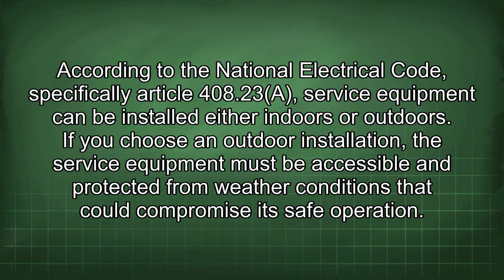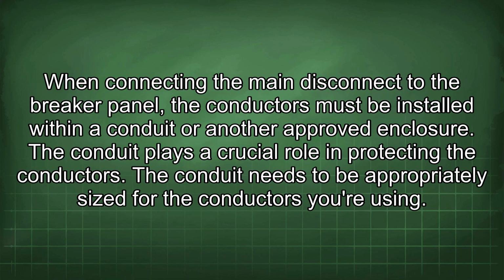According to the National Electrical Code, specifically Article 408.23a, service equipment can be installed either indoors or outdoors. If you choose an outdoor installation, the service equipment must be accessible and protected from weather conditions that could compromise its safe operation. When connecting the main disconnect to the breaker panel, the conductors must be installed within a conduit or another approved enclosure. The conduit plays a crucial role in protecting the conductors.